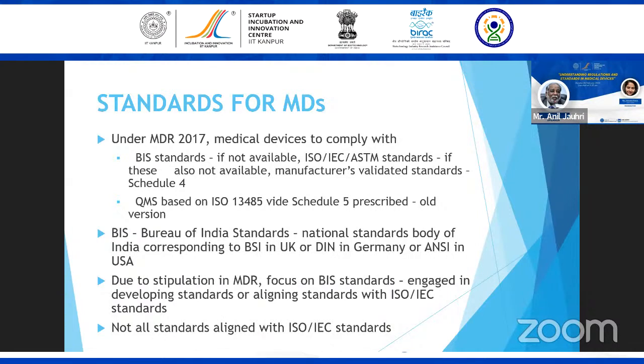There is another schedule, which is 5, which says a quality management system has to be followed. It prescribes the quality management system, which is largely based on ISO 13485, but the old version, unfortunately. This is the 2003 version of ISO 13485. Now we are in the new version of 13485, which is the 2016 version. So that's a slight dichotomy in the regulations, that the QMS required is as per the old version, whereas 13485 now is a new version.